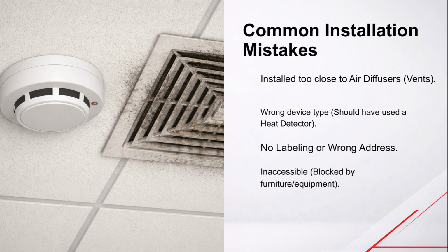Beyond air vents, there are other installation mistakes to avoid. One is accessibility. I often see detectors installed above tall shelving, huge machinery, or in spots that require a special lift to reach. If a technician cannot safely reach the device to test it or clean it, that device is effectively useless. Another mistake is using the wrong device type, like putting a smoke detector in a boiler room where a heat detector should have been used. And finally, labeling. If the detector is labeled Room 101, but it is actually in Room 102, emergency responders will go to the wrong place.